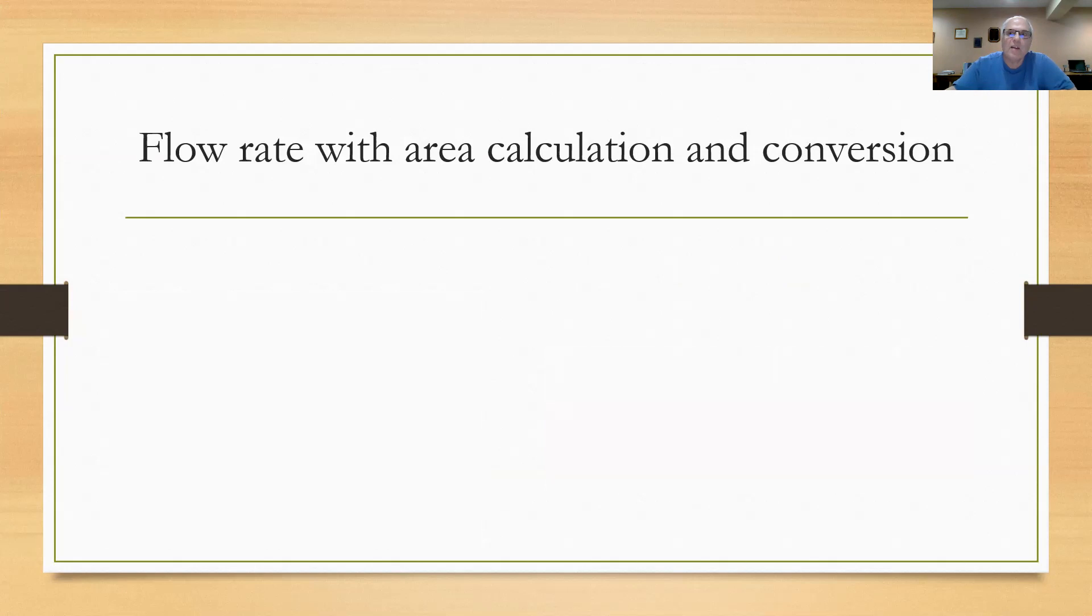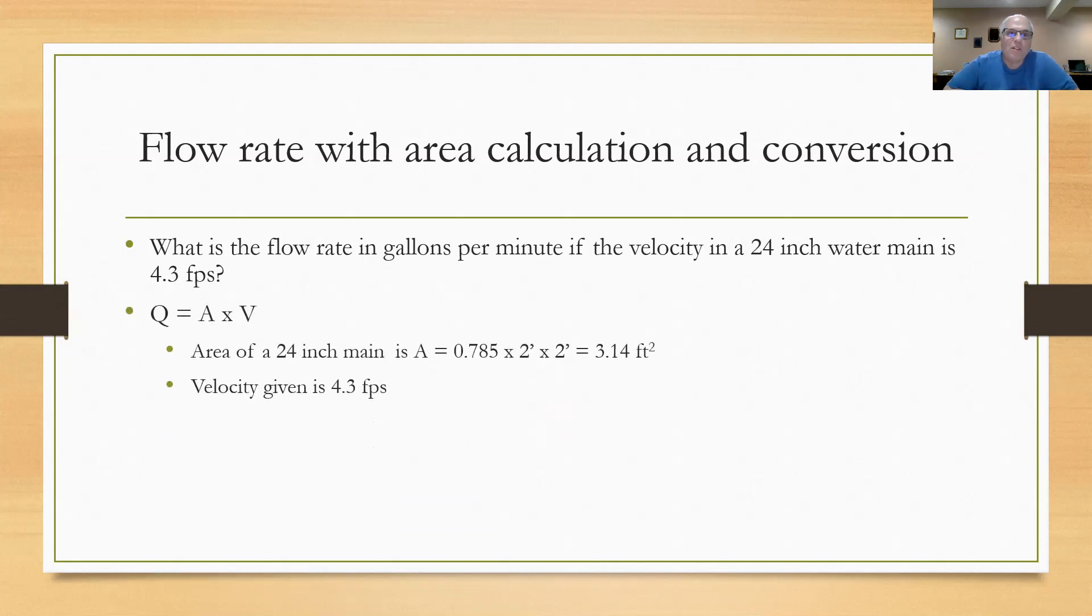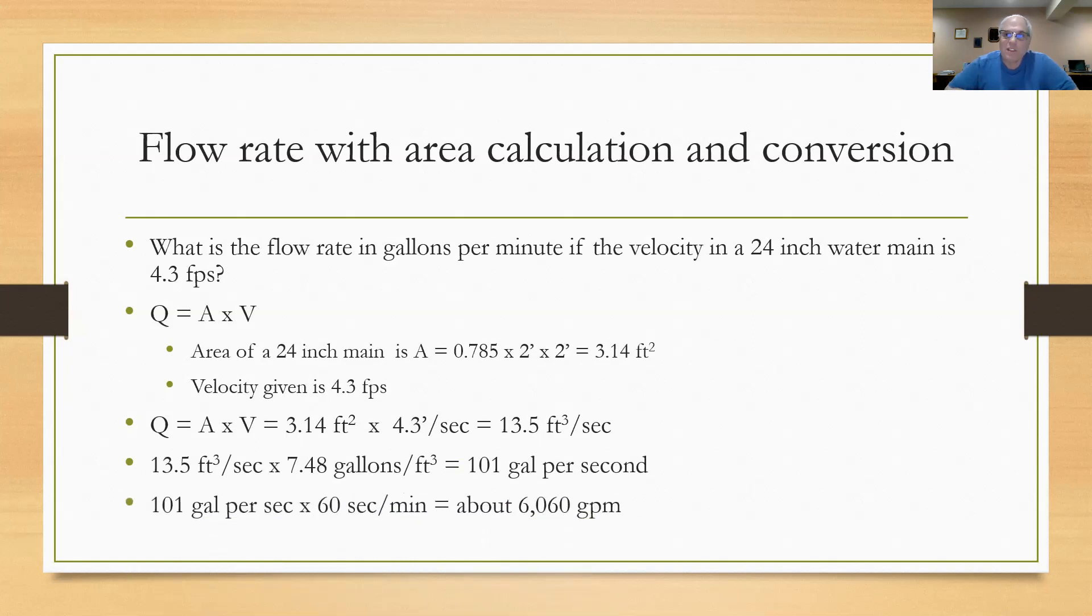Here's a flow rate conversion where I've got to calculate the area and then convert. What's the flow rate in gallons per minute if the velocity in a 24-inch water main is 4.3 feet per second? Using Q equals A times V, I calculate the area of the 24-inch main by multiplying 0.785 times the diameter squared. It's a two-foot diameter, so I multiply 2 times 2, coming up with 3.14 square feet. With velocity at 4.3 feet per second, I multiply 3.14 square feet times 4.3 feet per second and get 13.5 cubic feet per second. I had to calculate the area first, then multiply by velocity. To change cubic feet per second to gallons per minute, I take 13.5 and multiply by 7.48, getting 101 gallons per second. Then multiply by 60 to get approximately 6,060 gallons per minute.